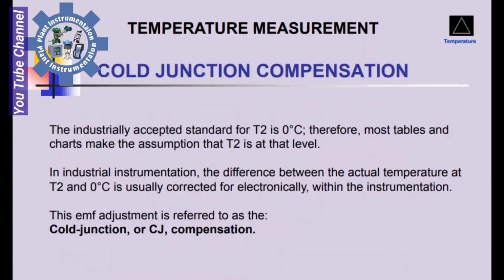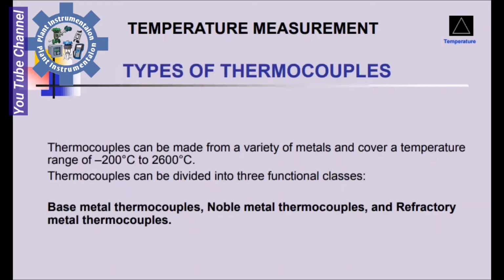Cold junction compensation. The industrially accepted standard for T2 is 0 degrees centigrade. Therefore, most tables and charts make the assumption that T2 is at that level. In industrial instrumentation, the difference between the actual temperature at T2 and 0 degrees Celsius is usually corrected electronically within the instrumentation. This EMF adjustment is referred to as the cold junction compensation, or CJC.